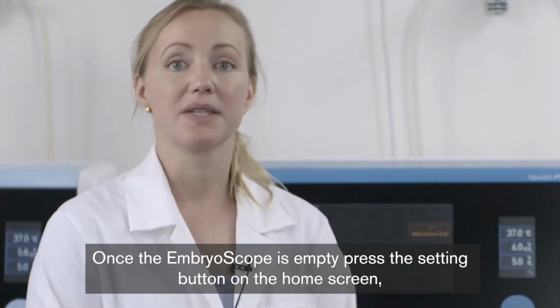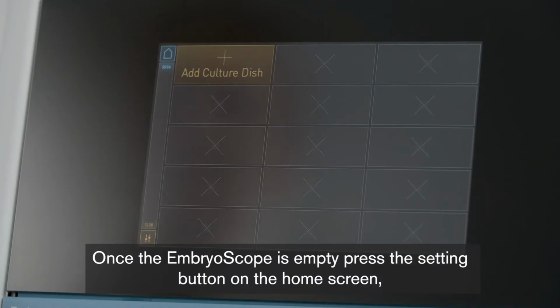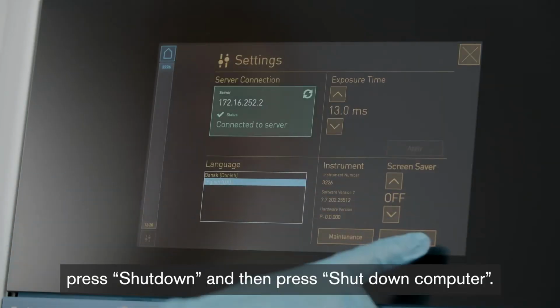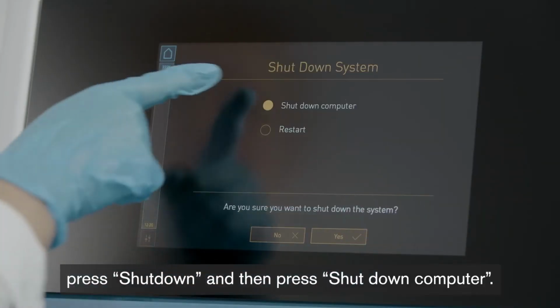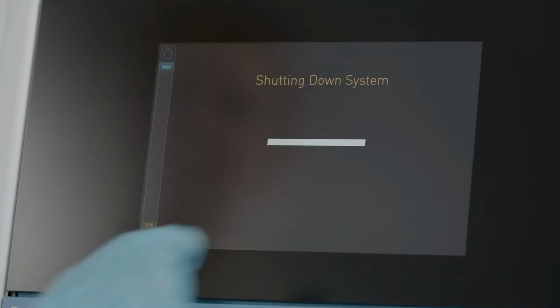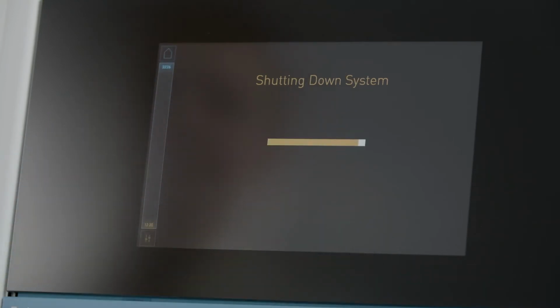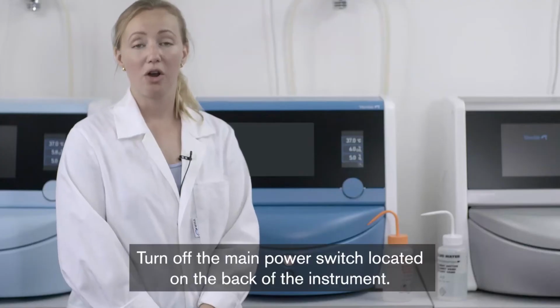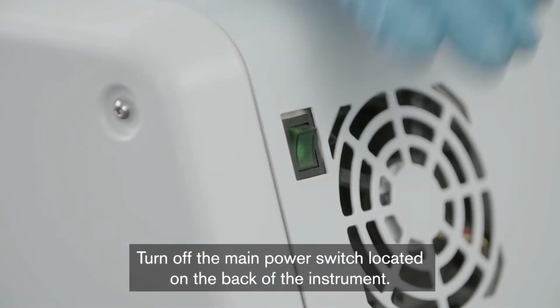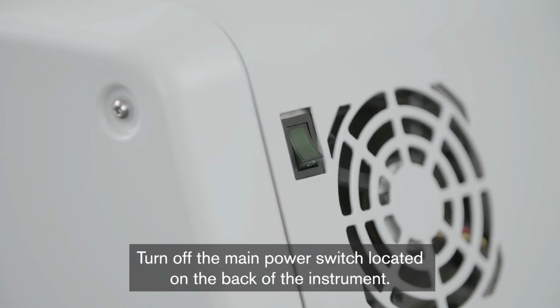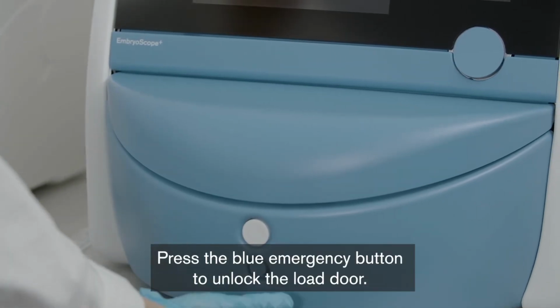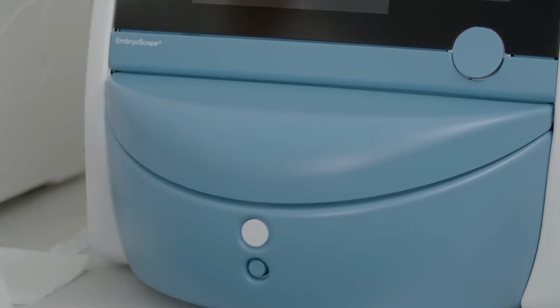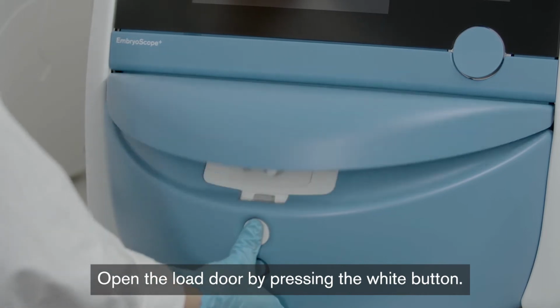Once the EmbryoScope is empty, press the settings button on the home screen. Press shut down and then press shut down computer. Turn off the main switch located on the back of the instrument. Press the blue emergency button to unlock the load door. Open the load door by pressing the white button.